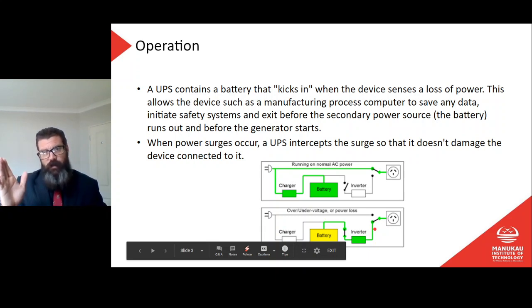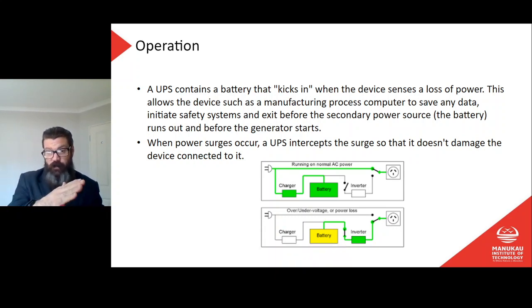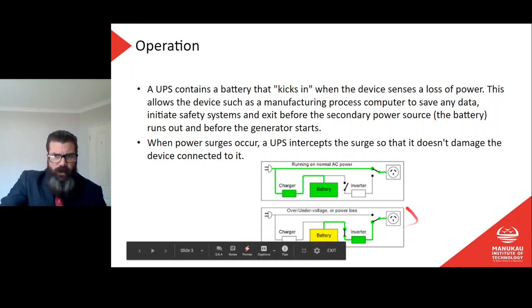So when power's on, it's this way. And when power goes off, the changeover switch falls the other direction. Really common for automatically switching power supplies, generator supplies, that kind of thing. Anyway, so the power goes off, that contact falls to that side. This, while also closed, that switch there may also be run off the same relay coil, so that it automatically closes when the relay coil loses power, and then battery power will go through the inverter and through to our supply there. Easy, eh?